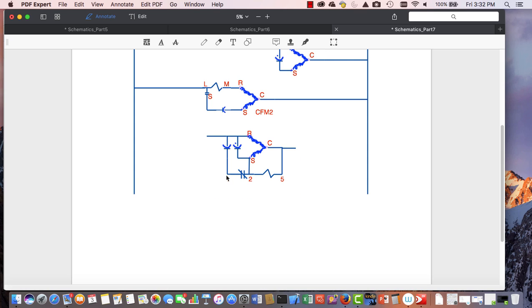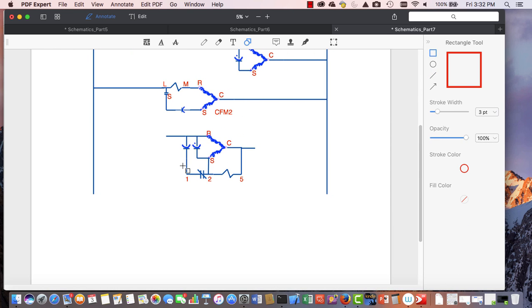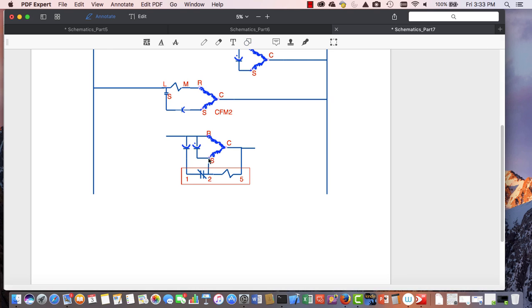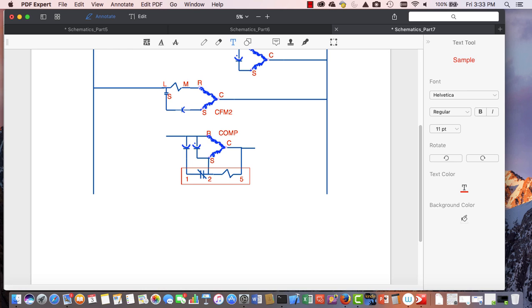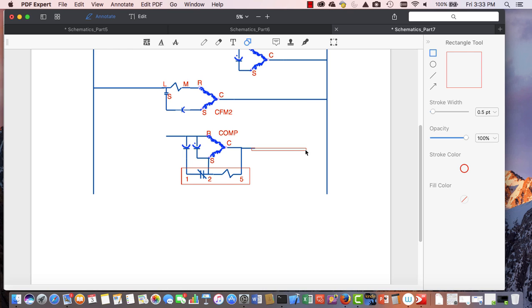Now, this component at the bottom here, the 1, 2, and 5, that is a separate component that's wired in. If you want to, you can actually throw a box around that. Let's go ahead and pull that line size down a little bit. Okay, and that shows that it's a single component, with 1, 2, and 5. 1 is wired to my start cap, which is wired to my line. 2 is wired to the start winding. 5 is wired to the common. So this I'm going to go ahead and label real quick. It's my compressor. Okay, and I'm going to then go ahead and connect this in. Okay, I want to select line again.